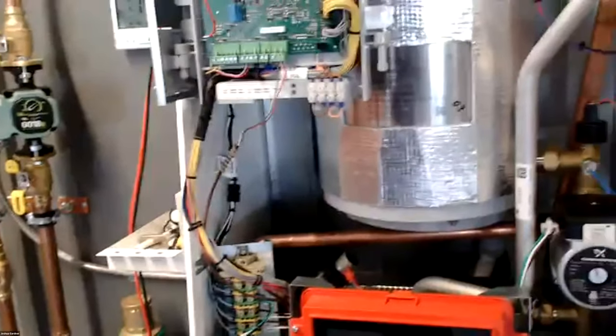So we have all the true labeling, the flame connection threw everybody off. But essentially that was your CH1 pump, and the CH1 pump was being used as your boiler pump. So now we have those two terminals in there that make sense. And we also have the CH2 pump installed. So out of the boiler and all our new boilers, you can run two zones of heat, the system circs, your boiler pump, and a DHW pump right out of the box. If you're doing zone valves, you'll either have to add a relay or use a ZVC control to tie those in, because we only send out 120 volts. You don't have an option for 24 volts there for your zone valves.